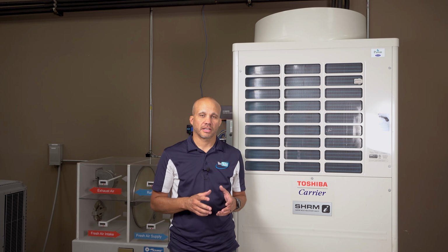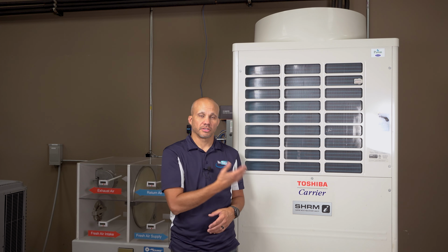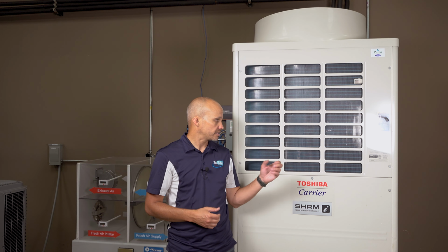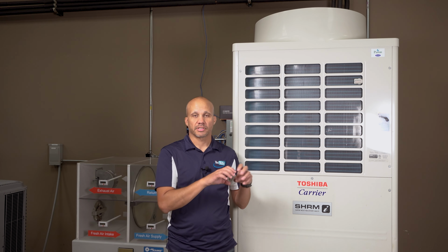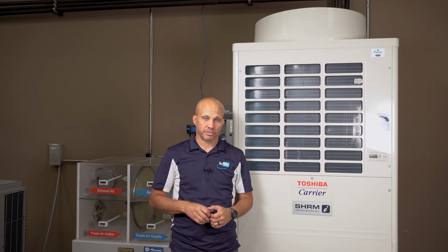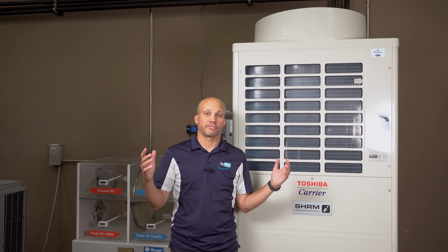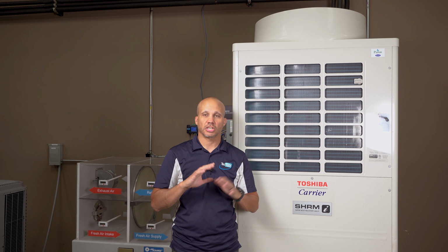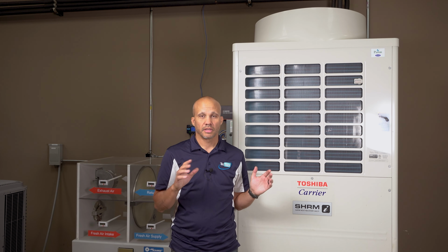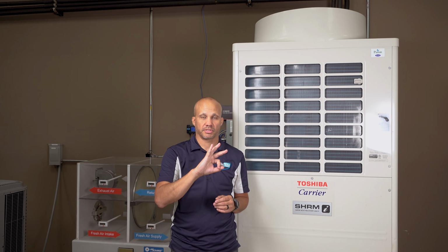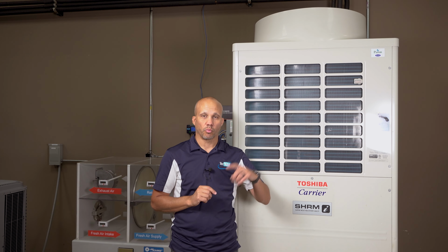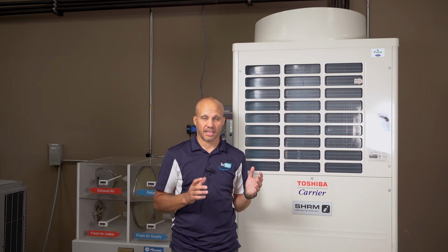Now let's take that ductless concept to larger systems. This is a variable refrigerant flow system, or just nicknamed VRF. This is an outdoor unit that happens to be piped to numerous indoor units. It could be 5, 10, 20, 30 of these indoor units. And it can send the cold refrigerant or warm refrigerant to them, just like all the other heat pumps that we talked about. This one, however, happens to be a 3-pipe system, which means that it can send both cold refrigerant to some zones and warm refrigerant to other zones at the exact same time.